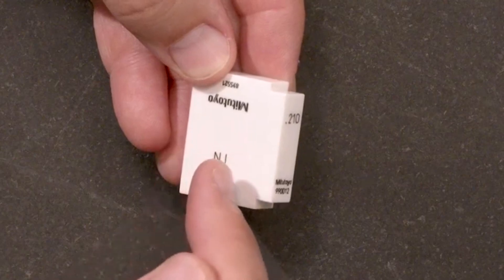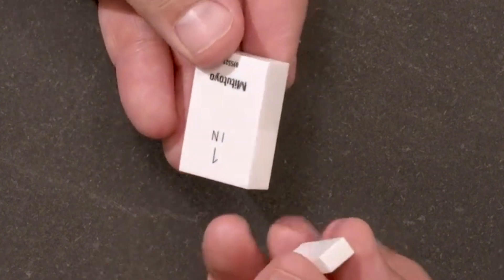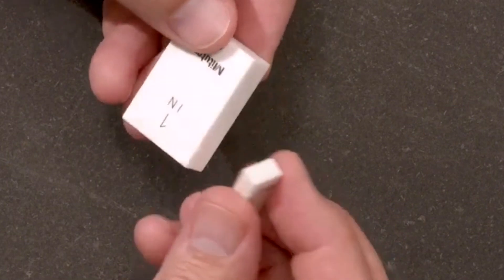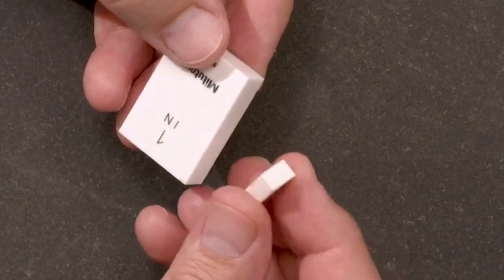When you're all done using the wrung gauge blocks, you can just slide them back apart like this. If you leave the blocks wrung together for, say, several days or more, it can become very hard to take them apart. So don't leave them wrung for too long.